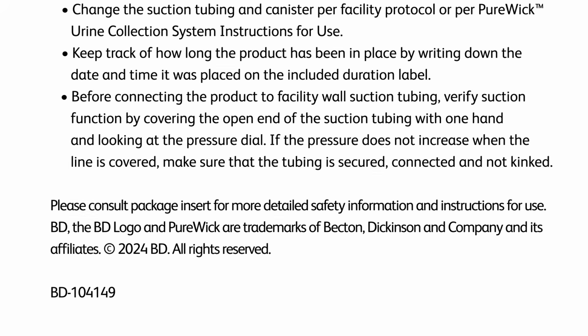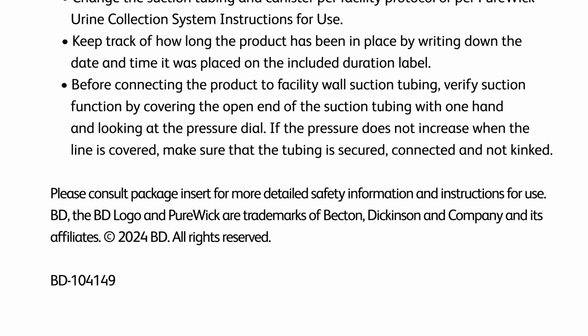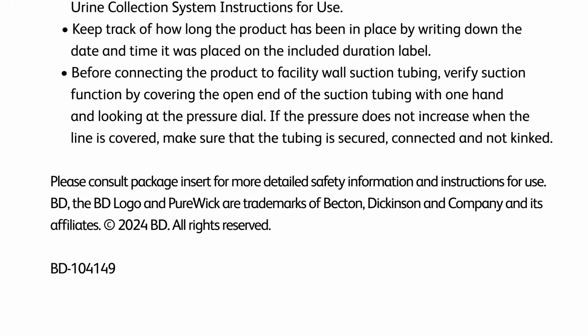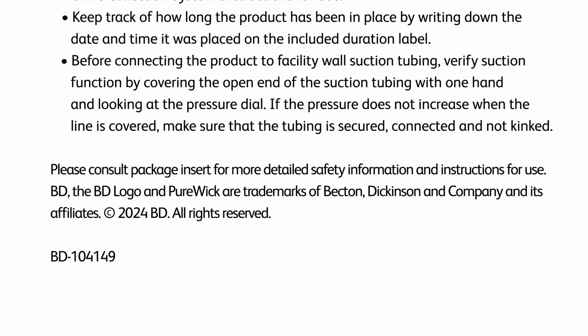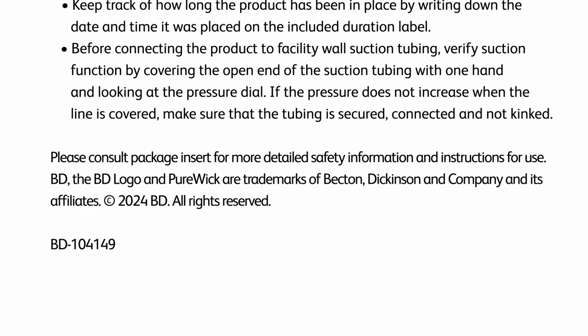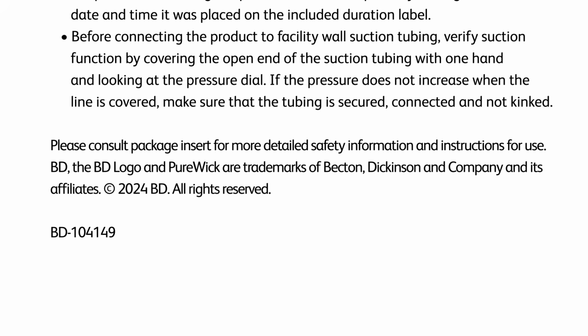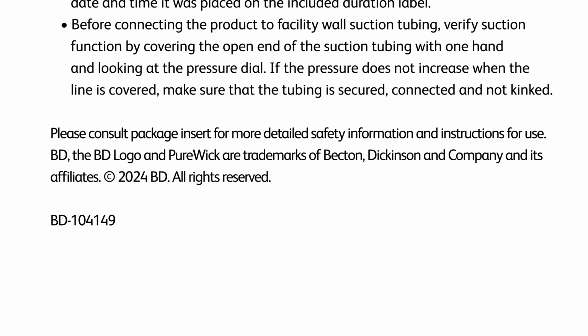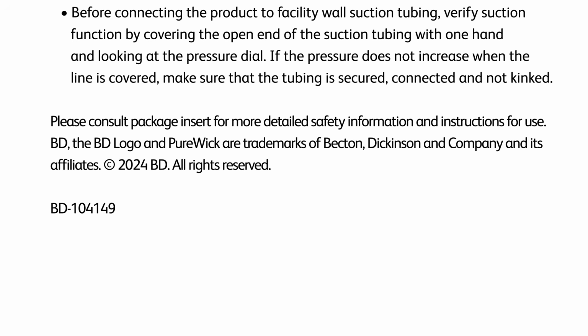Before connecting the product to facility wall suction tubing, verify suction function by covering the open end of the suction tubing with one hand and looking at the pressure dial. If the pressure does not increase when the line is covered, make sure that the tubing is secured, connected, and not kinked.